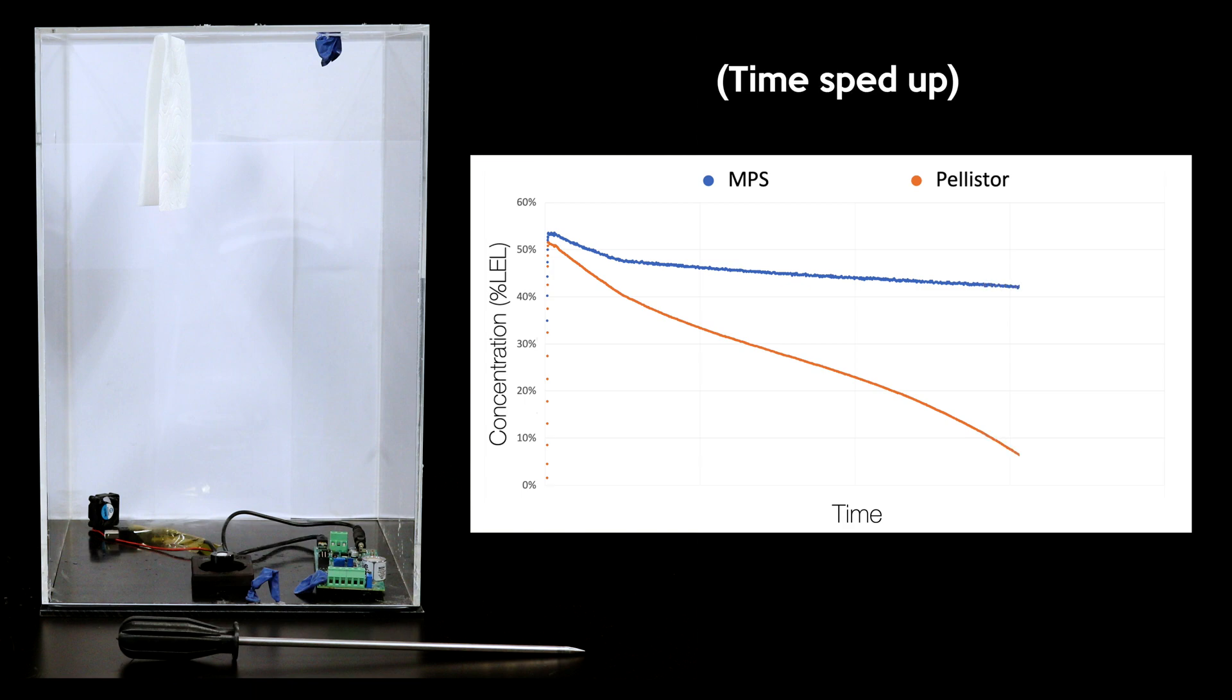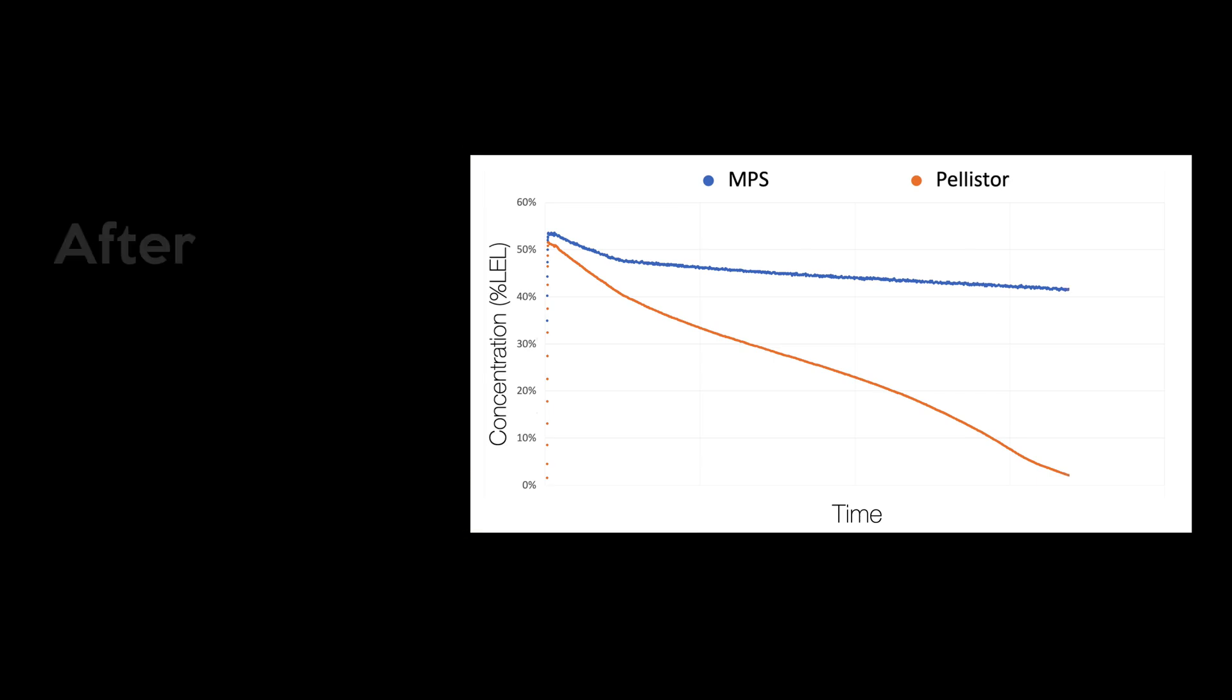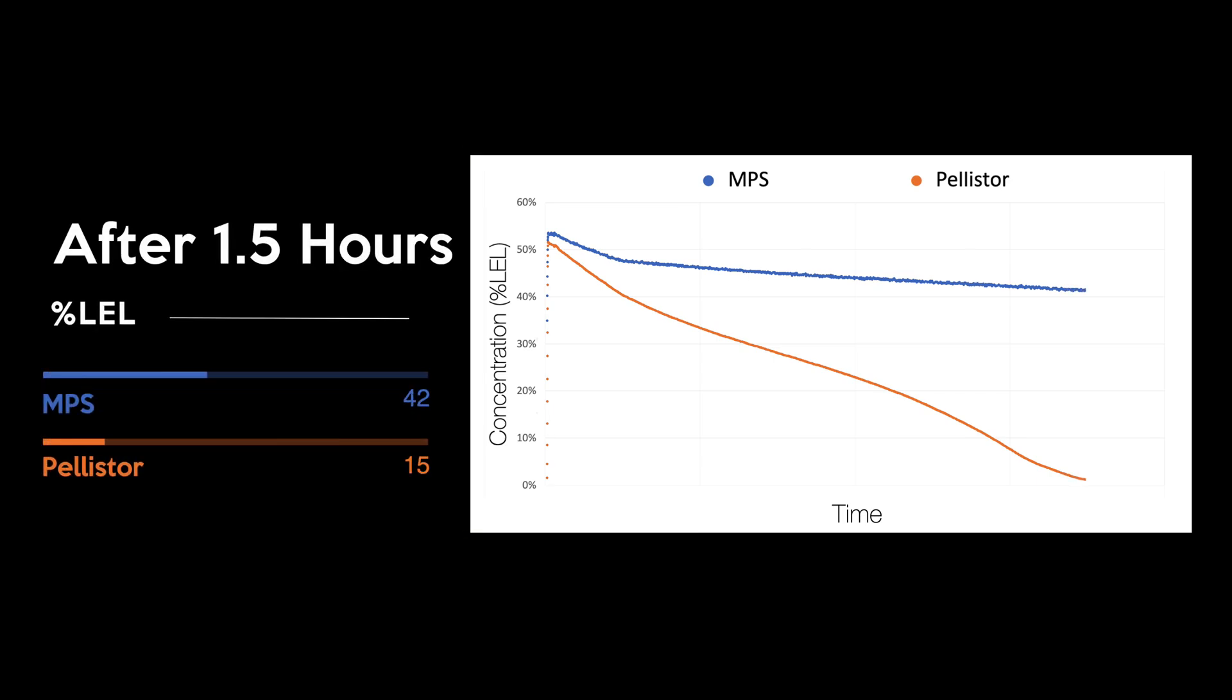Methane slowly leaches out of the chamber over the course of the test since it isn't perfectly airtight. After an hour and a half, the pellistor is reading 15% LEL while the MPS is reading 42% LEL.